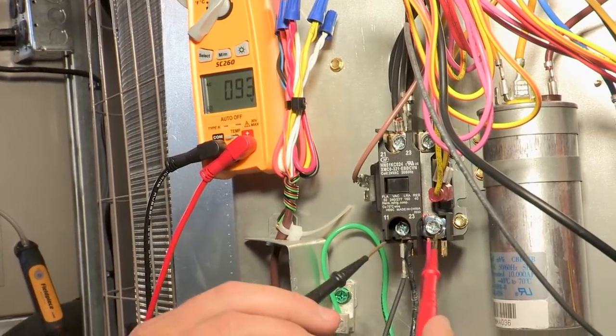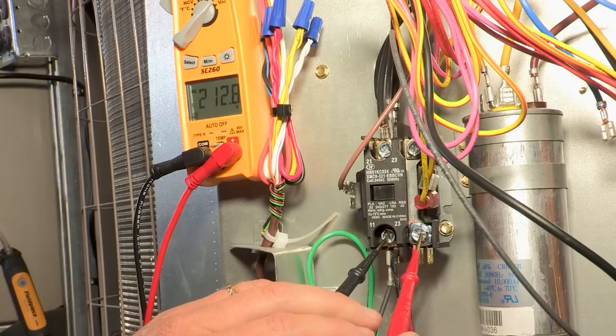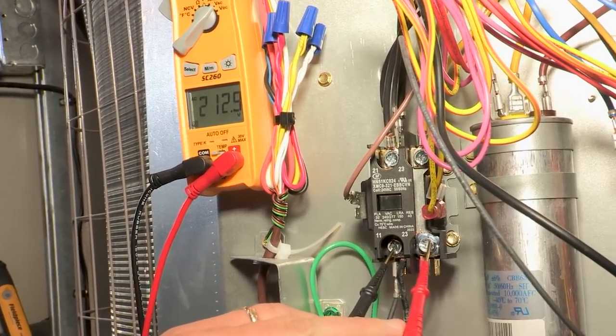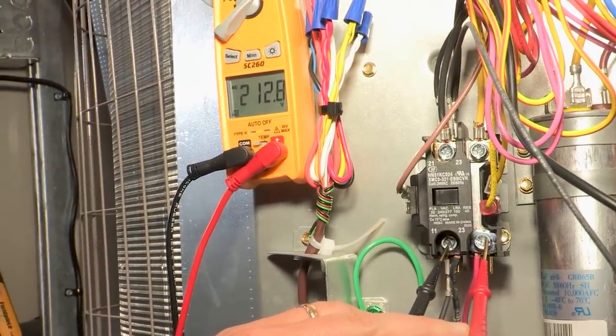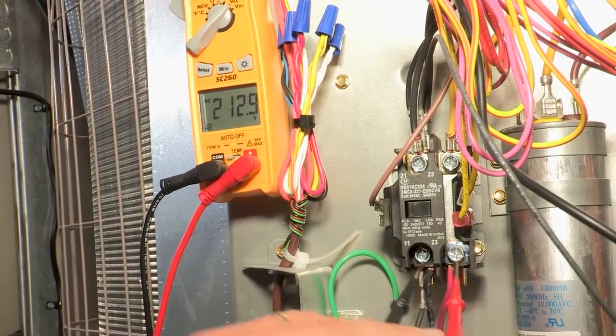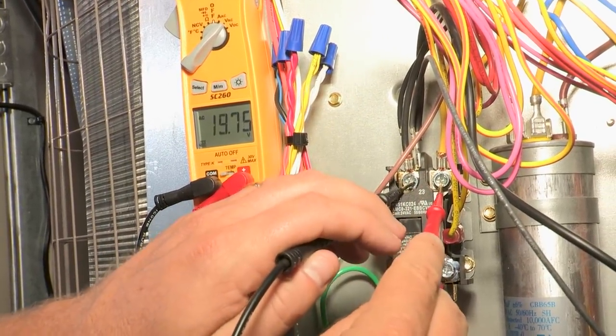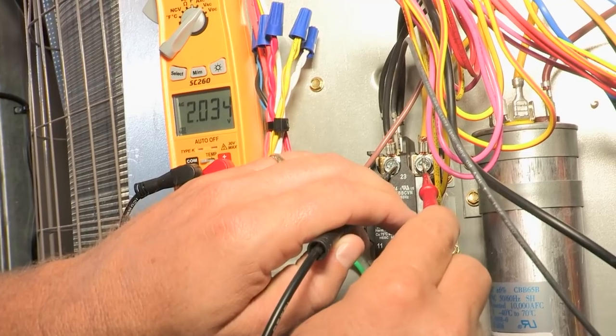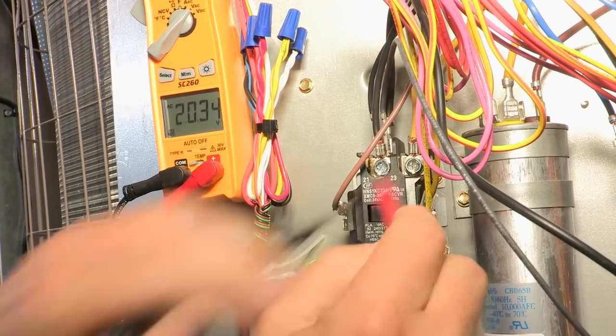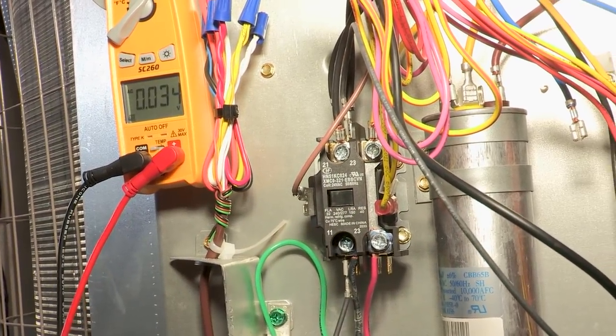We're just going to confirm at the bottom. Sure enough, because this is a commercial building, we have 208, so that's why we're seeing 212. Up here, we're going to have nothing. I mean, next to nothing, because our contactor is not pulled in.